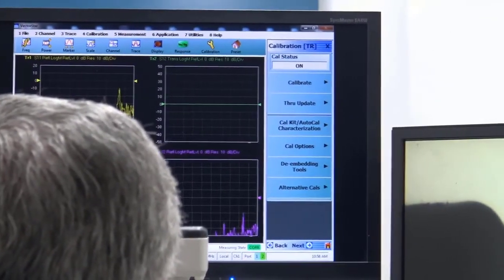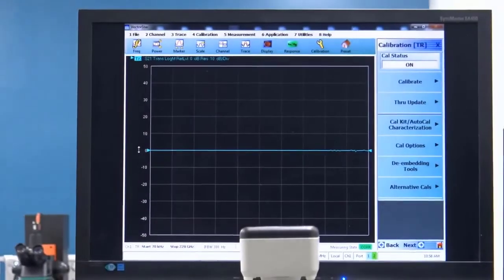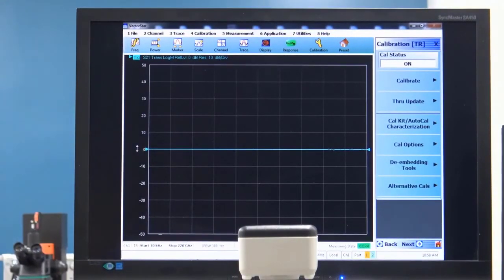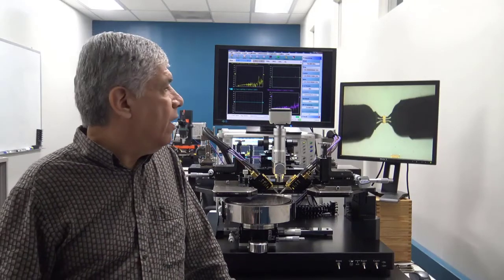So trace 3 is now showing a measurement of the calibration through, which of course is going to look excellent, because that's what we're using as our standard. So you can see with the proper calibration substrate, the calibration of the ME7838G 220 gigahertz system, the VectorStar Broadband system, is very similar to our other broadband systems, and doing a calibration at 110 gigahertz or 220 gigahertz, it's still the same process of having a calibration substrate where you can do, for instance, an LRM calibration and get very good results over the entire frequency sweep in a single sweep measurement.